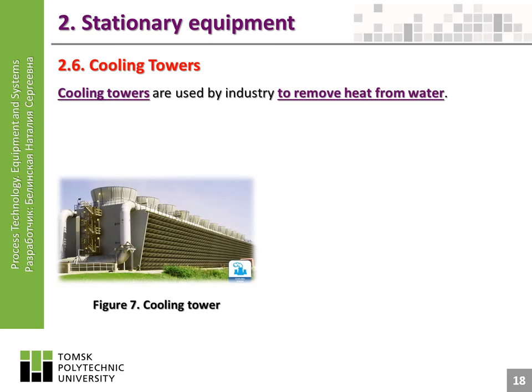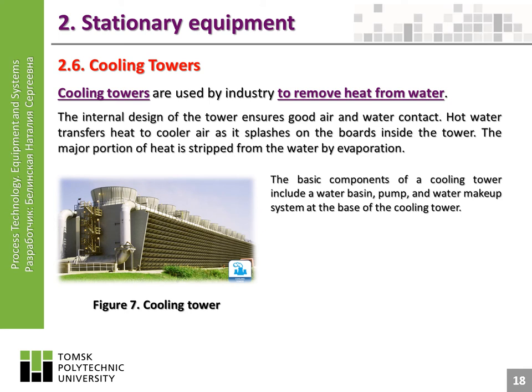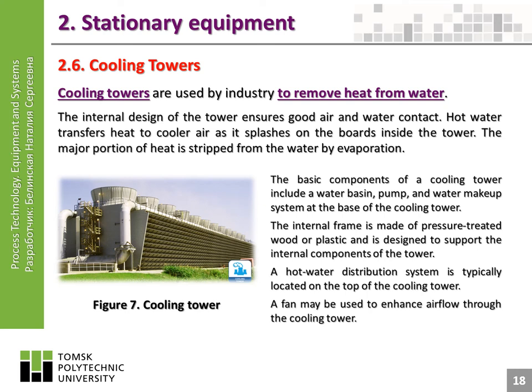Cooling towers are used by industry to remove heat from water. The internal design ensures good air and water contact. Hot water transfers heat to cooler air as it splashes on the boards inside the tower, and the major portion of heat is stripped from the water by evaporation. The basic components include a water basin, pump, and water makeup system at the base, an internal frame of pressure-treated wood or plastic, a hot water distribution system at the top, and a fan to enhance airflow.